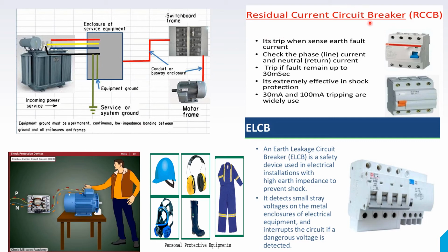Residual current circuit breaker. It is also called RCCB. It is a very important device in case of earth fault current. It trips when it senses earth fault current. It checks the phase current and neutral current. It trips if the fault remains up to 30 milliseconds and more. It is extremely effective in shock protection. 30 milliampere and 100 milliampere tripping are widely used.